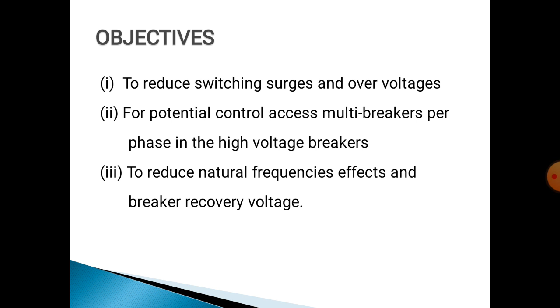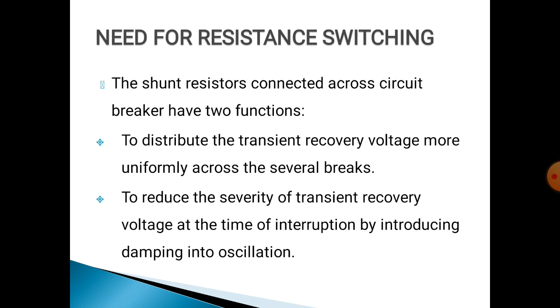And the next important thing is the need for resistance switching. There are two main needs. First, to distribute the transient recovery voltage more uniformly across the several breaks, and next, to reduce the severity of transient recovery voltage at the time of interruption. That means if any fault occurs on that line, the circuit breaker senses the current, so at the time of interruption, the severity of transient recovery voltage is reduced by introducing damping into the oscillation. These are the needs for resistance switching.